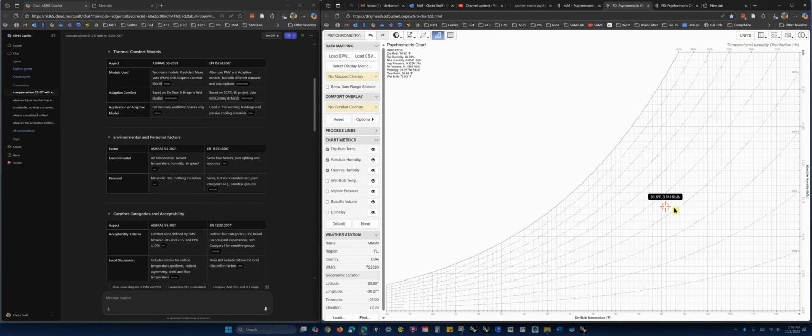Dew point is another thing that I think can be confusing. So let's play with it for a second. If I'm at 80 degrees Fahrenheit, 40% relative humidity, what is my dew point? It says here that it's 54 degrees. Why is that true? Well, if I'm just looking at the chart, I can go straight over along this line and I get to about 54 degrees. Well, it says 54.13. I'm not exactly at 80, so if I go up a little bit, yes, I'm about here. So that would be right. So that line is what's creating my dew point.